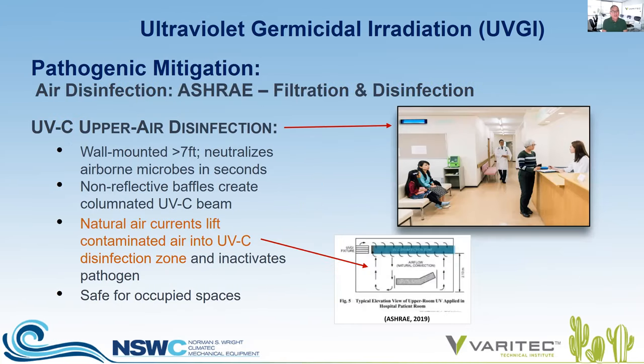You can use UVC light in upper air disinfection. You want to locate these devices at a minimum of seven feet above the floor, but you can actually neutralize aerosolized pathogen within the room literally within seconds — not minutes, not hours. By applying a non-reflective baffle at the bottom of the device, you can focus that UV ray upward and outward so that the light does not enter the occupied zone where it could present a potential health concern. You also want to optimize mixing in the space so you're always drawing aerosolized pathogen from the room up into the upper levels where it can be exposed to the UVC beam and deactivated.